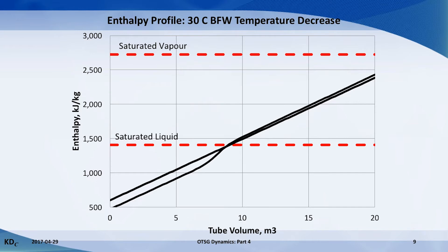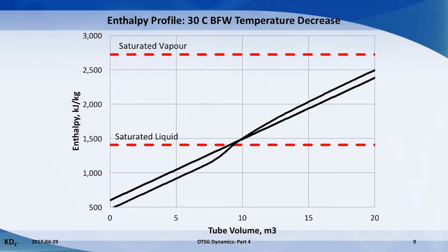This will require the OTSG to accumulate an additional 1 cubic metre of water. This also means that there will be less water available to flow downstream for keeping the radiant section cool. The cold front pushes through the boiling point and the water accumulates.